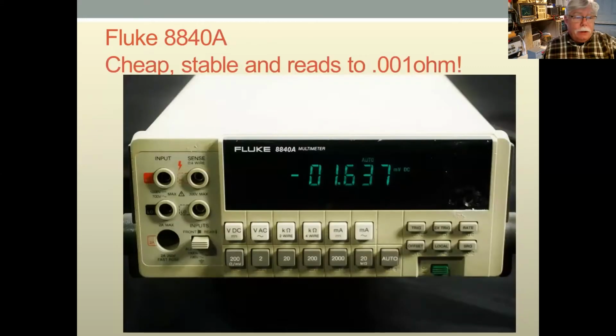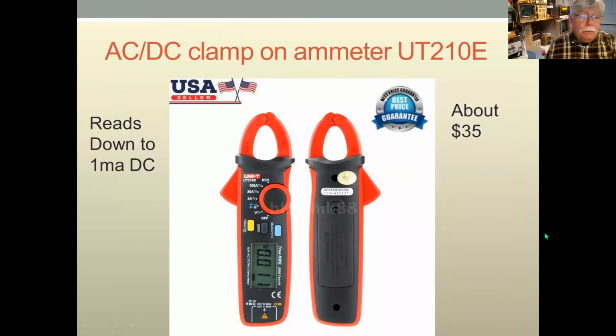Here's one for the benchtop, another Fluke, the 8840A. A lot of these were military and a lot weren't, but that doesn't necessarily mean military ones are bad. Just try to get one in good shape; some have been kicked around quite a bit, but get one that looks nice and it'll probably operate nice. They very rarely need fixing. They're 5.5 digit meters, stay in calibration, and have 4-wire ohms readings and null compensation and things like that. They're a very good bench meter, maybe all you'd ever need.